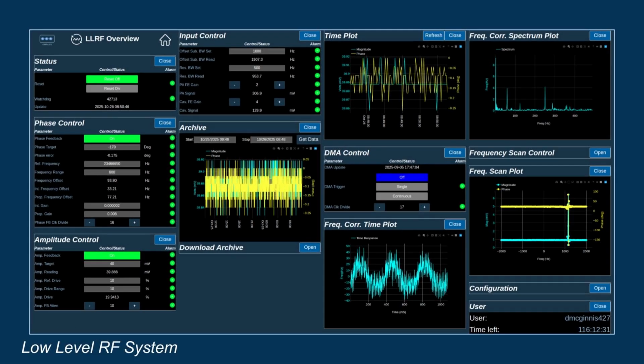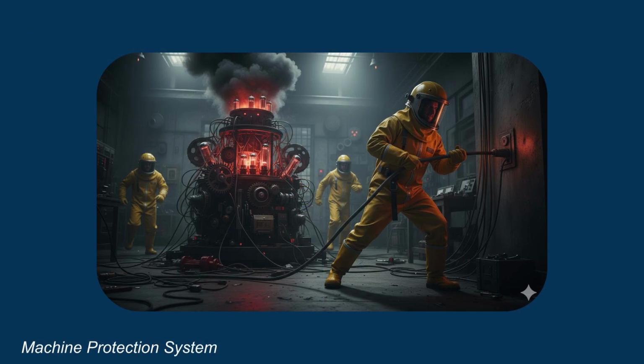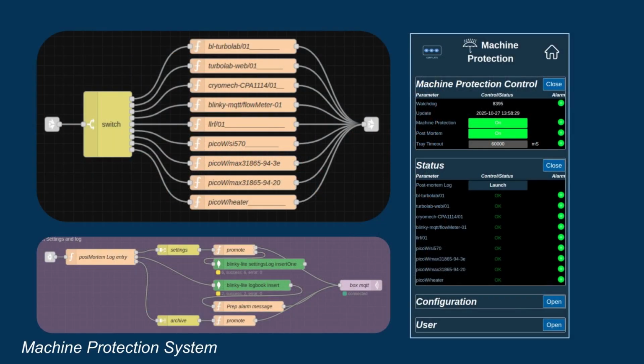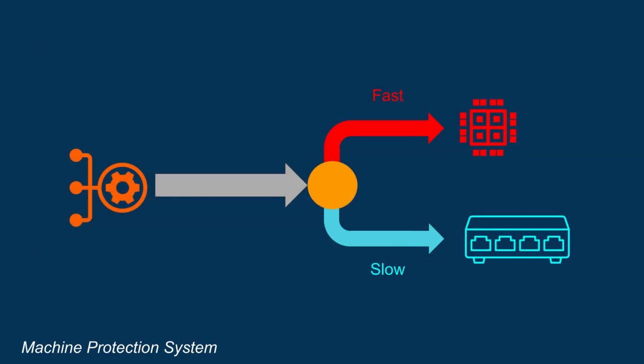With the LLRF system in place, our attention turns to the MPS, or machine protection system. The MPS is a very good example of how you can add custom automation to Blinky-Lite. The MPS is a vital system that safeguards fragile accelerator equipment, such as the superconducting RF cavity. This system must be robust, flexible, and designed for long-term operations. The core machine protection strategy is divided into two prongs: slow protection and fast protection.